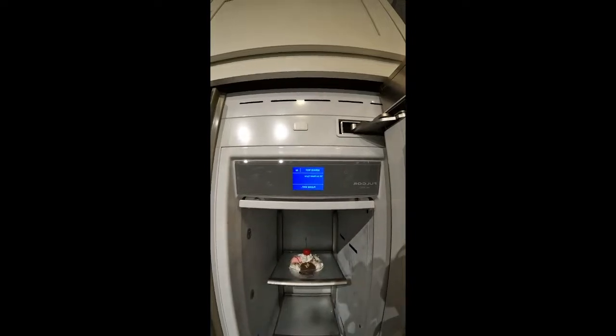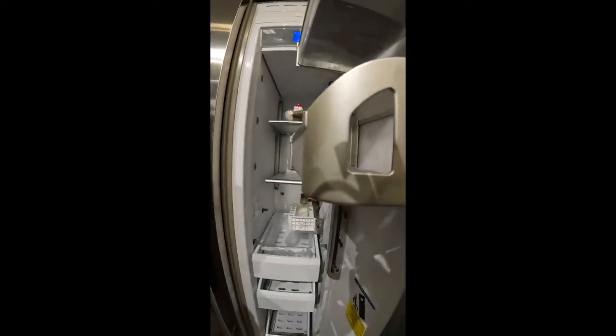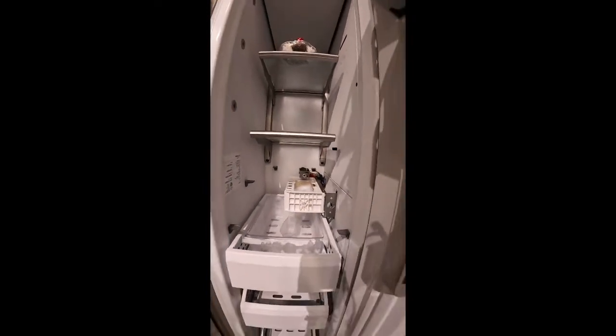So ice maker level, ice maker cycle. If you want to pan down, this will rotate and harvest the ice maker independently. It will not fill with water. It is just going to harvest and rotate the ice maker. Once again, it will not fill with water during this part of the test. It goes through a complete harvest. Once it's done harvesting, the display on the UI will say ice level low, and then you push OK to advance through to the next step. If you do not push OK in a timely manner, the ice maker will go through another harvest cycle.